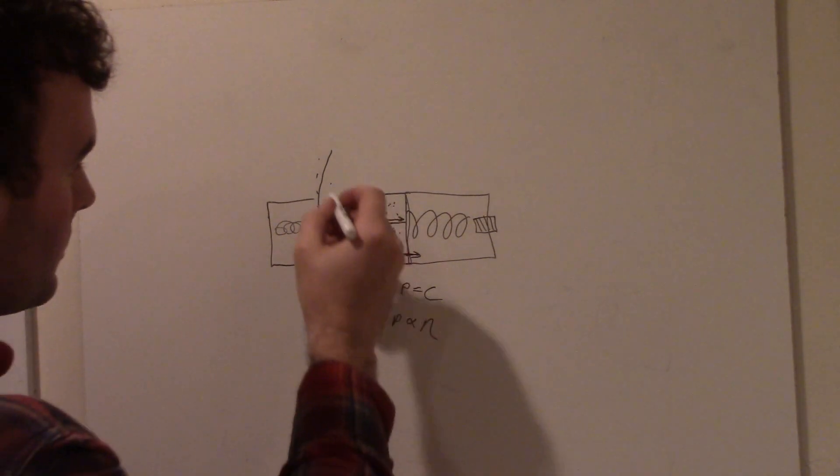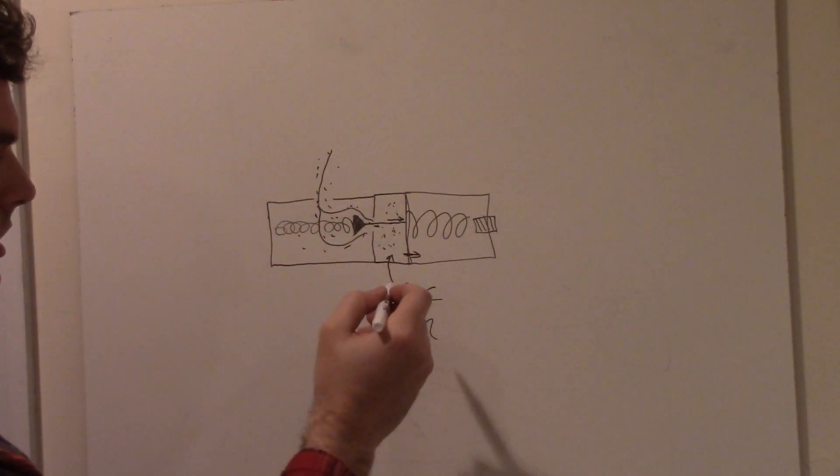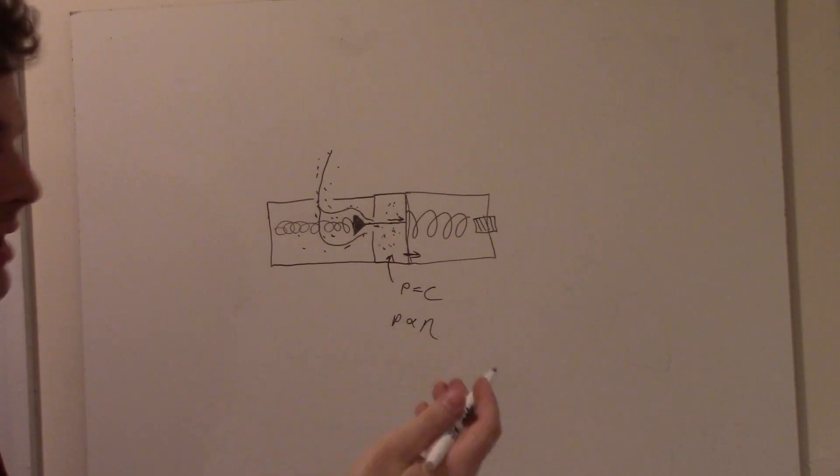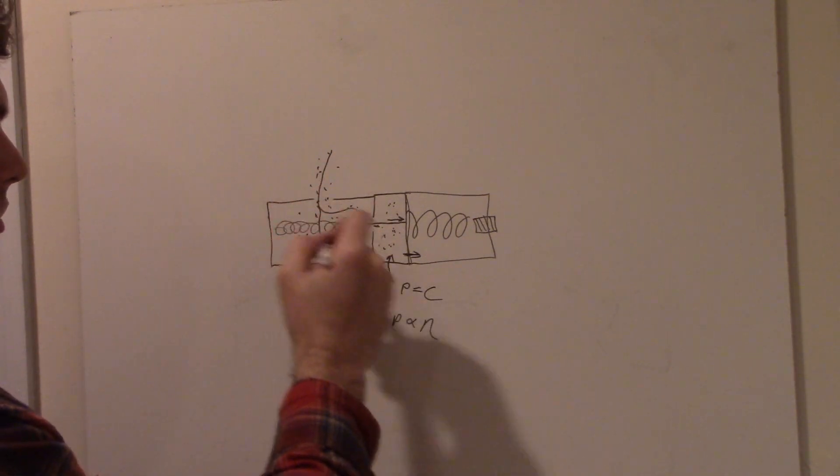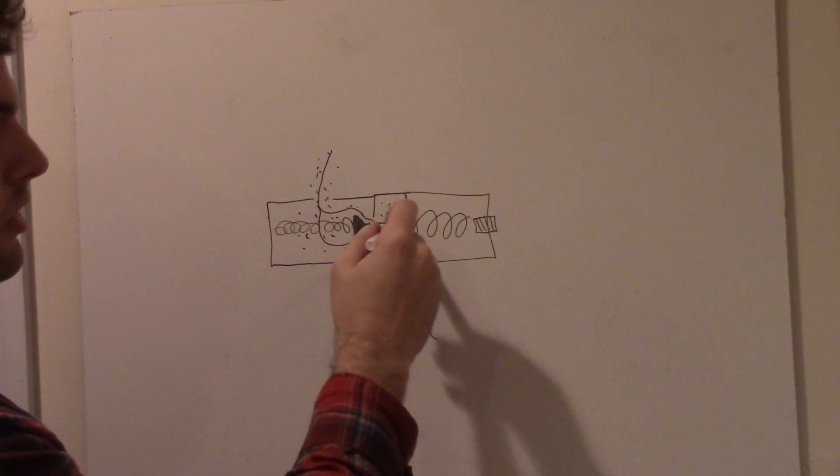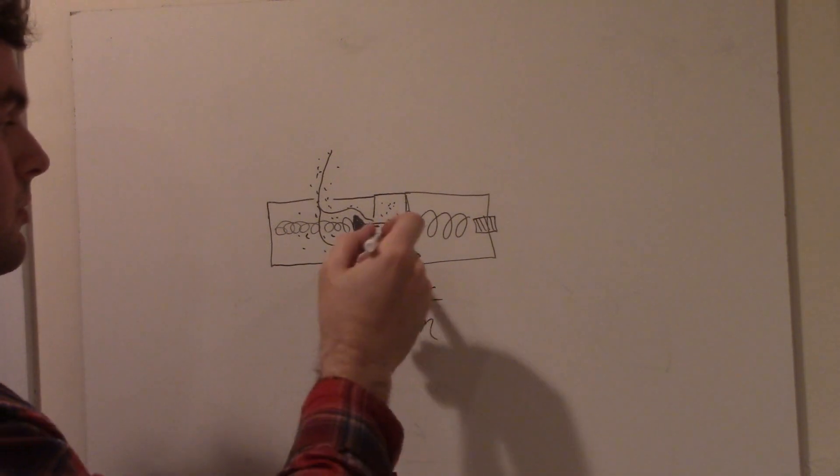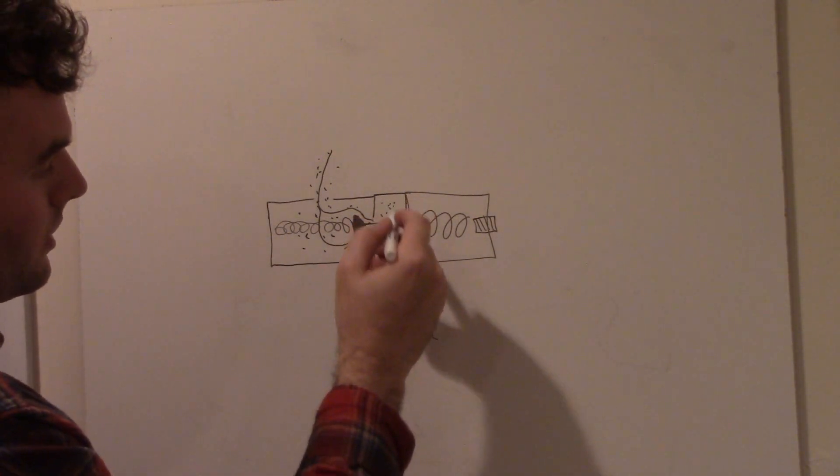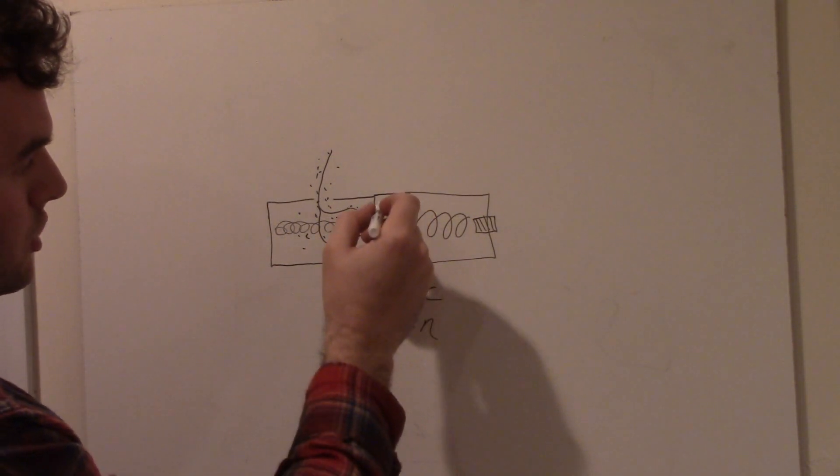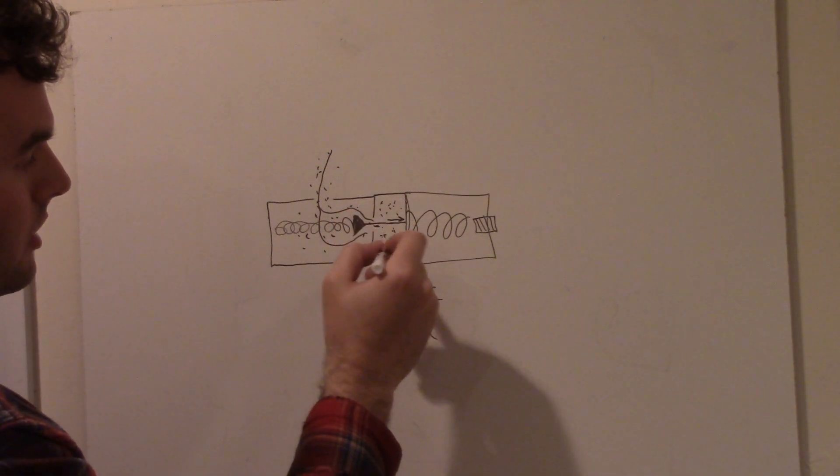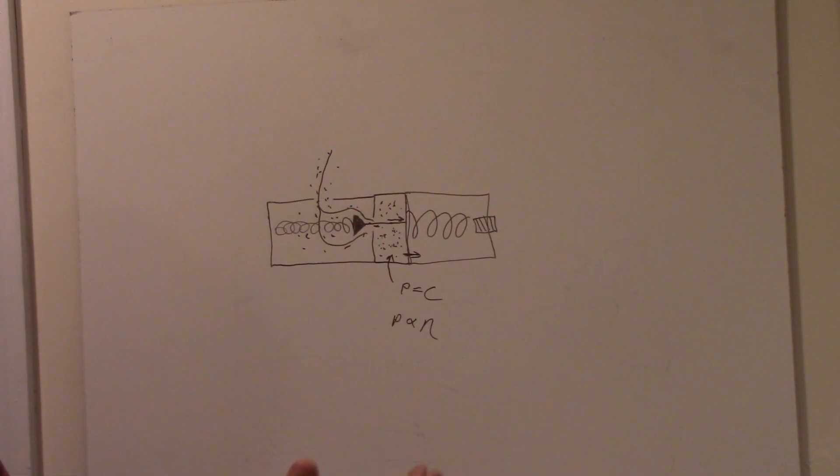The gas molecules start flowing in from the high pressure, flowing through into this region, until the force on this diaphragm increases enough that it helps this little spring overcome the force of this big spring. The diaphragm begins to move this way, which means that the valve gets smaller and smaller until eventually it would close.